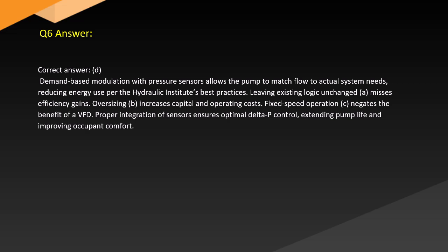Answer. Correct answer: D. Demand-based modulation with pressure sensors allows the pump to match flow to actual system needs, reducing energy use per the Hydraulic Institute's best practices. Leaving existing logic unchanged misses efficiency gains. Oversizing (B) increases capital and operating costs. Fixed speed operation (C) negates the benefit of the VFD. Proper integration of sensors ensures optimal delta P control, extending pump life and improving occupant comfort.